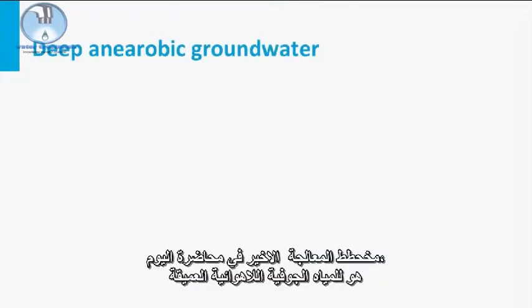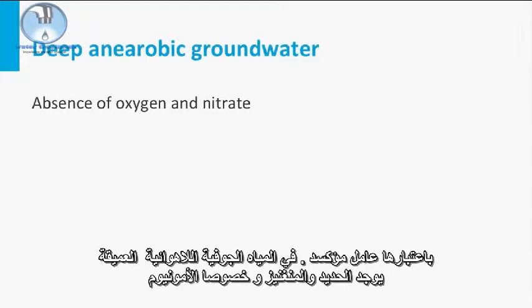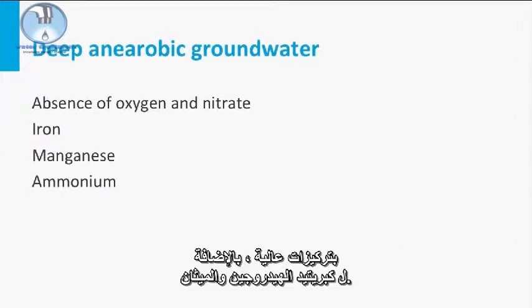The last treatment scheme in today's lecture is for deep anaerobic groundwater. Both oxygen and nitrate are absent in this groundwater, and organic material is broken down with sulphate as an oxidant. In deep anaerobic groundwater, iron, manganese, and especially ammonium are present in high concentrations, in addition to hydrogen sulfide and methane.